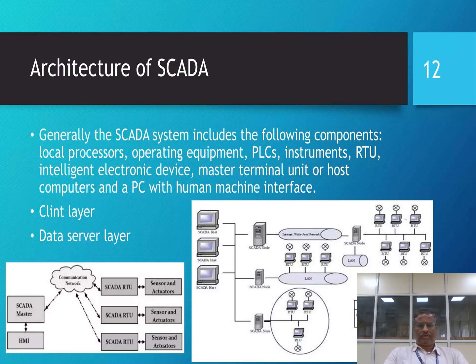In industries we have equipment for performing certain operations, so we need the equipment and the controllers. Only modern controllers, programmable logic controllers, actually interact with the equipment. None of the other controllers, like SCADA or HMI, can directly interact with the real-time physical devices or equipment available in the industries. So a PLC is a must if you want to implement SCADA for supervisory control of the entire plant.